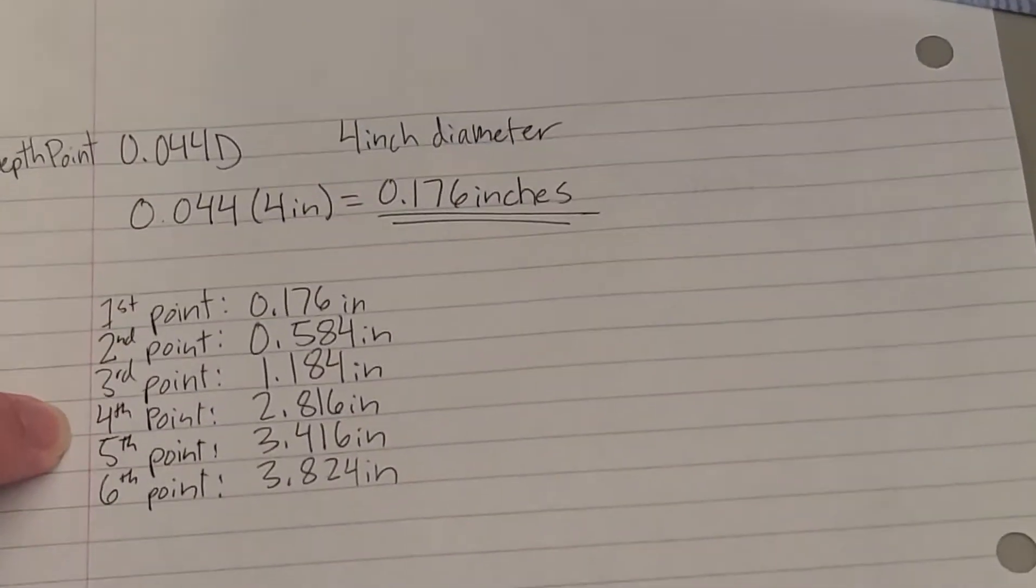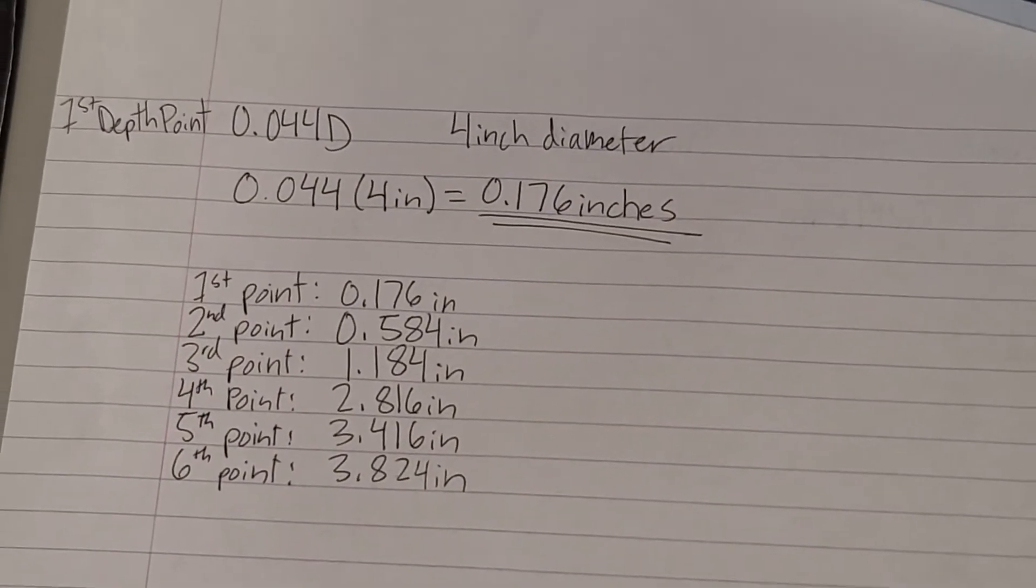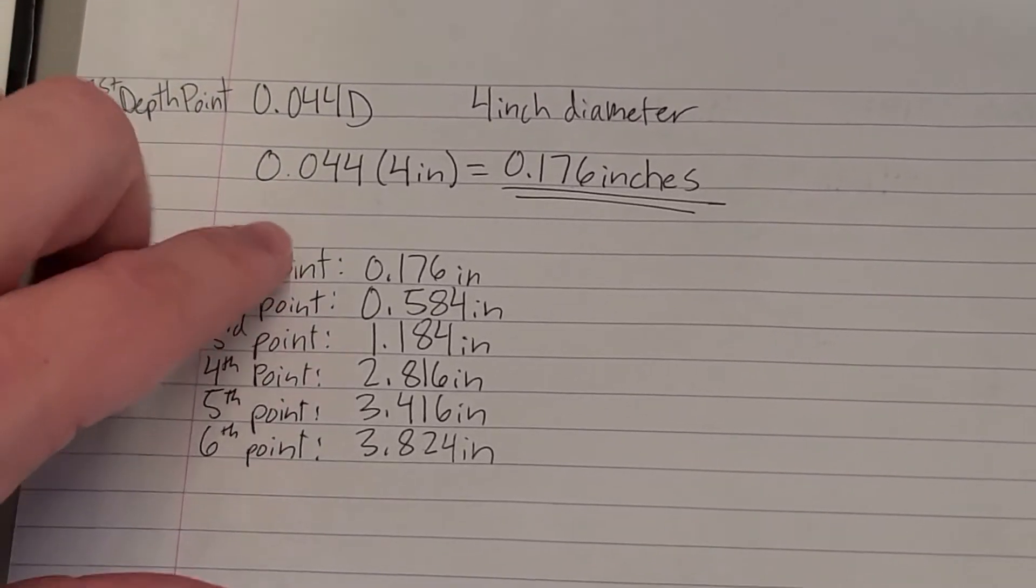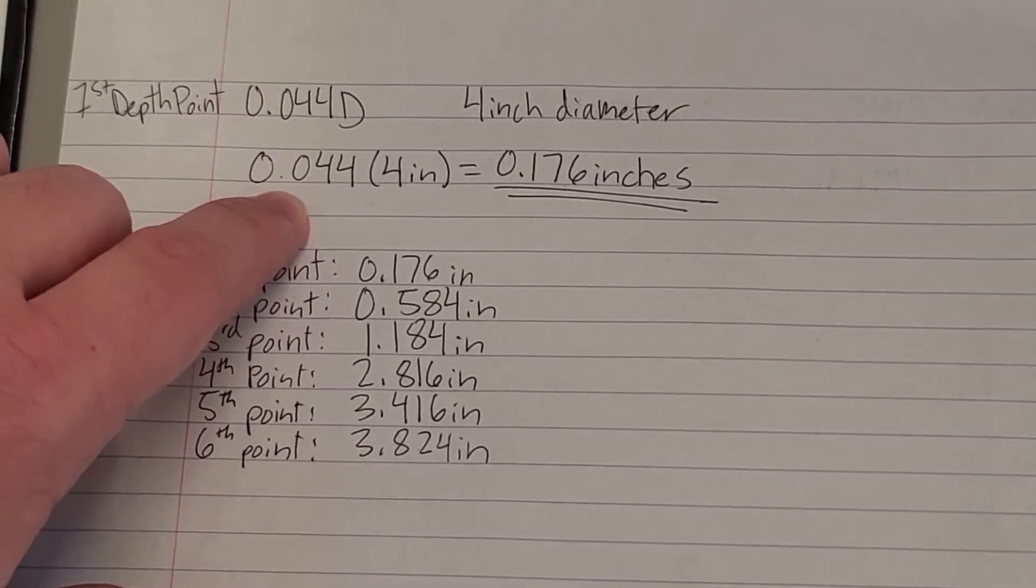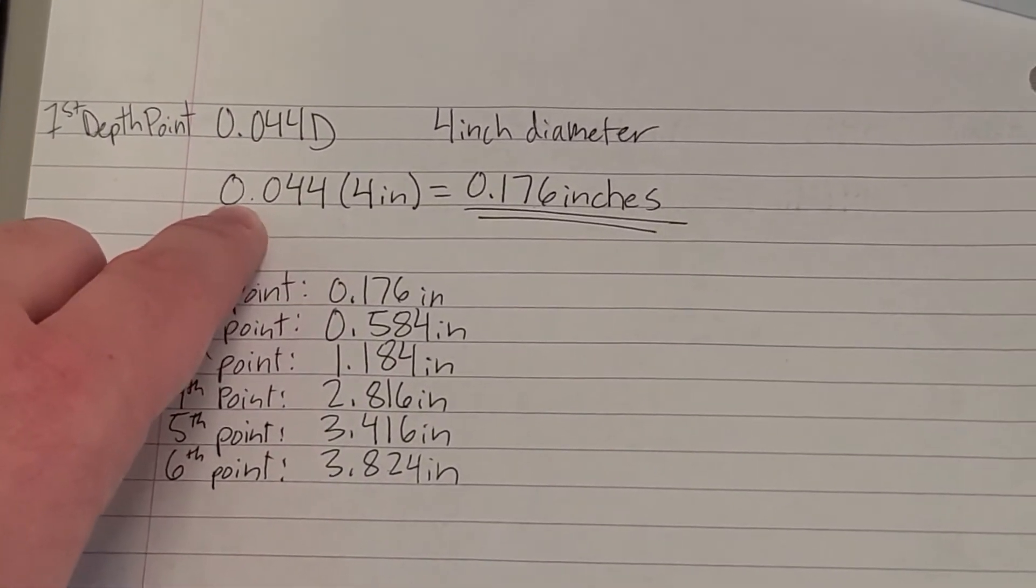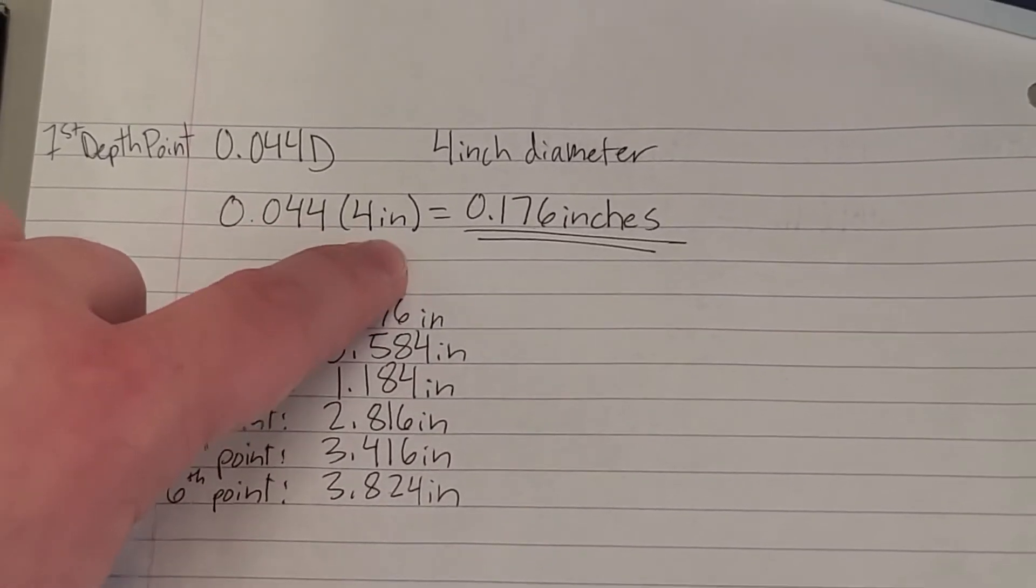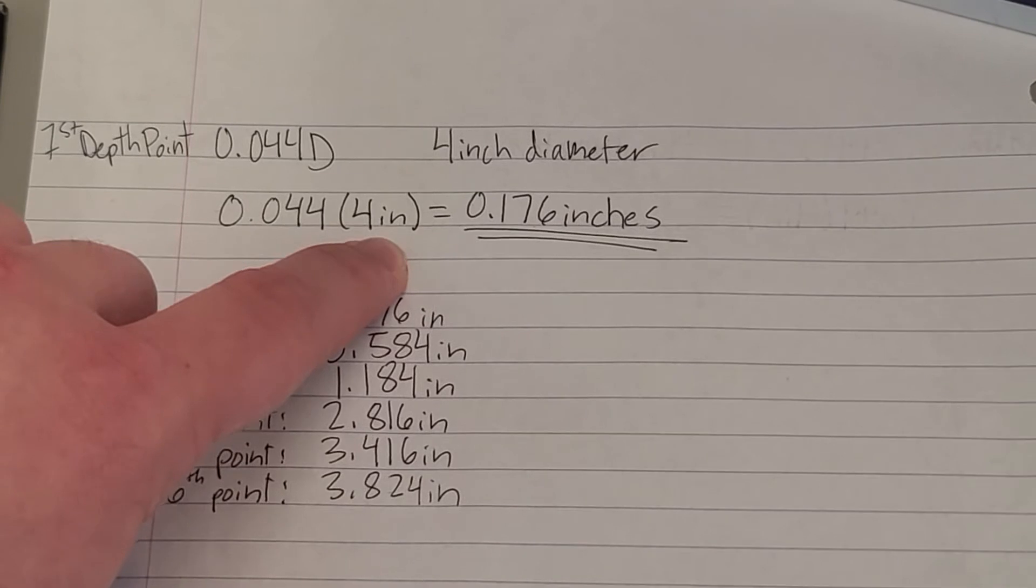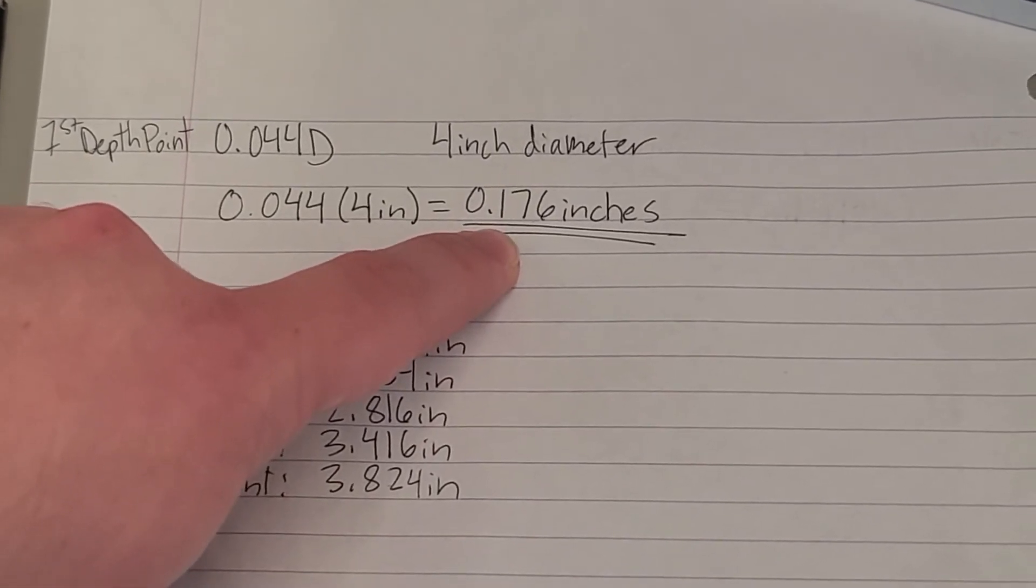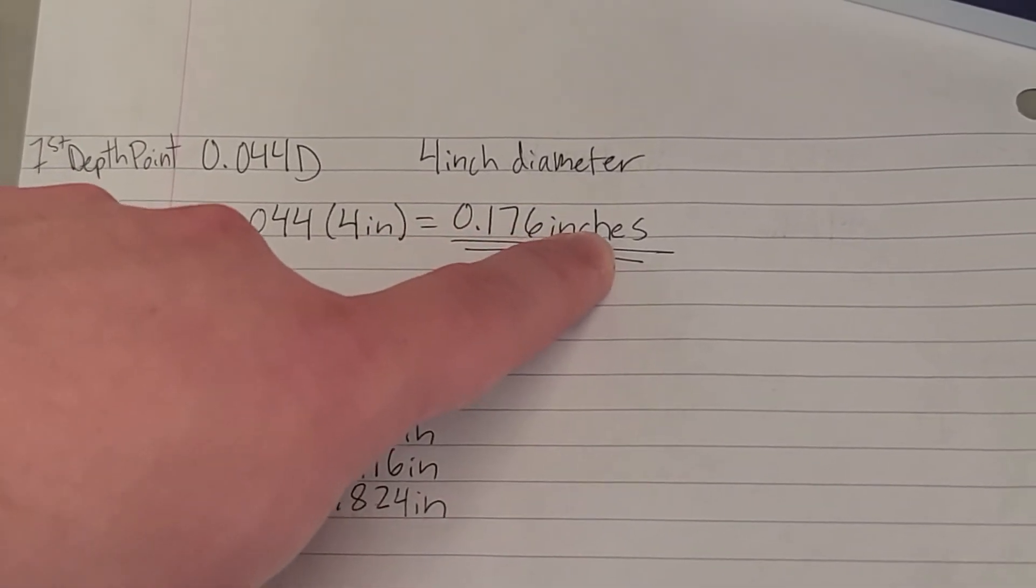Here we have some of the calculations for our duct specifically. Today we're using a 4-inch diameter duct, and we used the first point of the duct traverse to show how to calculate it. Here we see that 0.044 times our 4-inch duct diameter gives us a first point in the duct traverse of 0.176 inches.